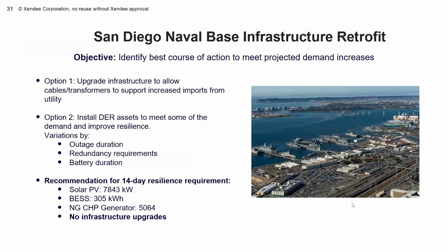So the second case that I want to show you here is, let's go through this very quickly. It's just really a naval facility here down in San Diego, a very old one. And it's a training facility. So the sailors need to go through training here before they get deployed. So they have critical buildings here for simulation, for certain kinds of simulation here. And they had to basically come up with a microgrid which can sustain a 14-day outage if the utility goes down, right? And they had two options. They could upgrade the distribution system or they go with a microgrid.